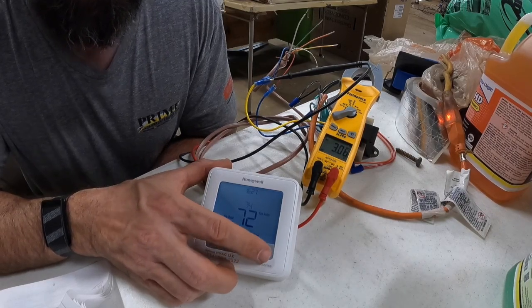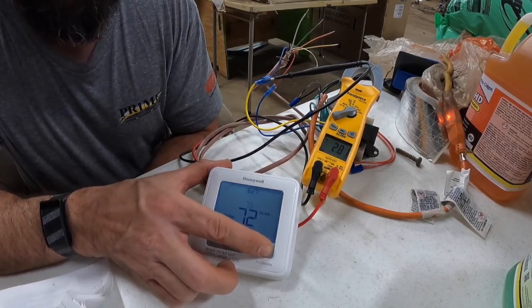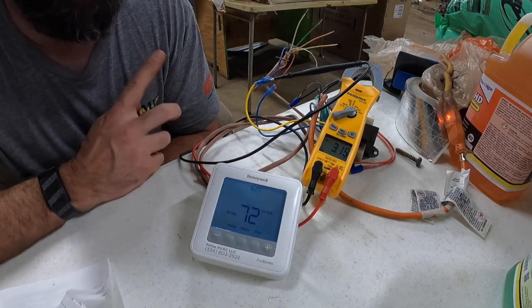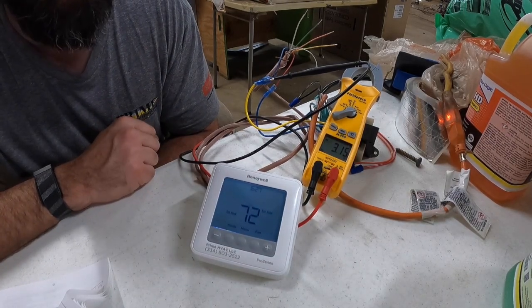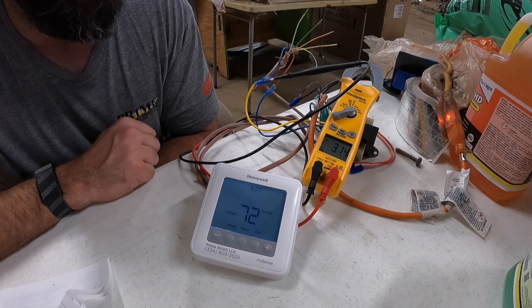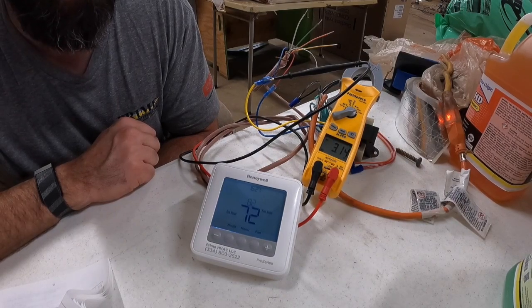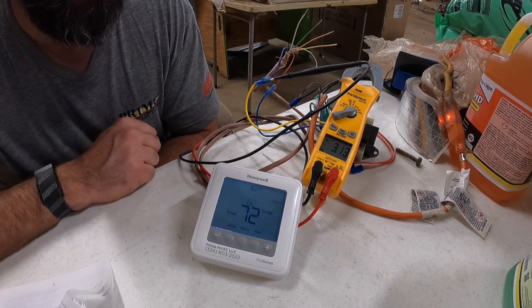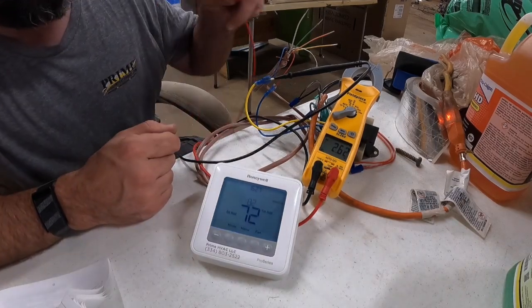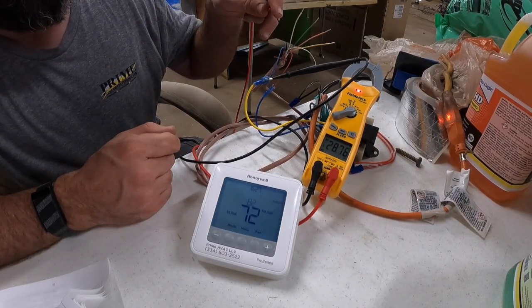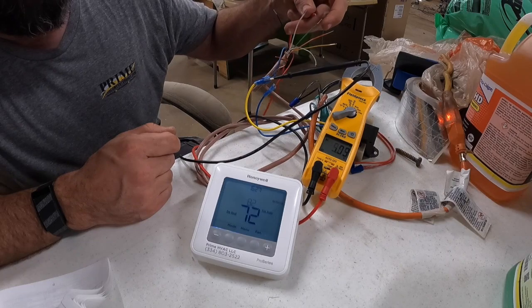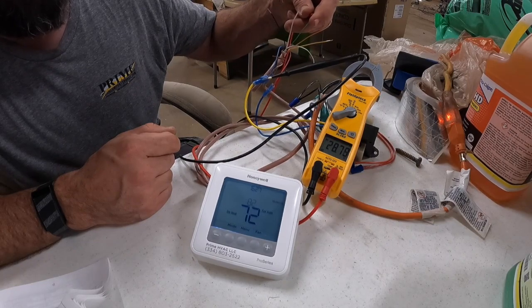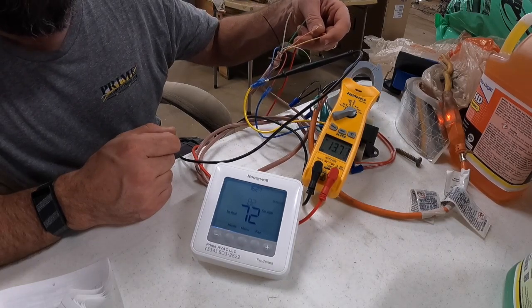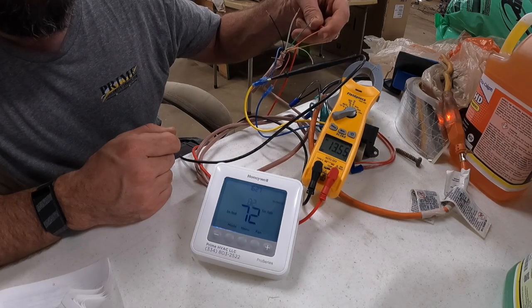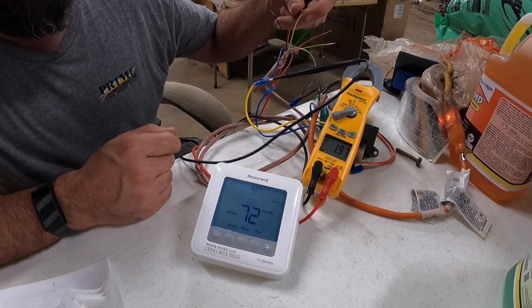Let's go to emergency heat. So we should just get the E terminal and the G terminal, which will be green and black, should be energized. Yep, emergency heat on. Yep, there's 28 volts there. There's 28 volts on G. Nothing on Y. Nothing on O.